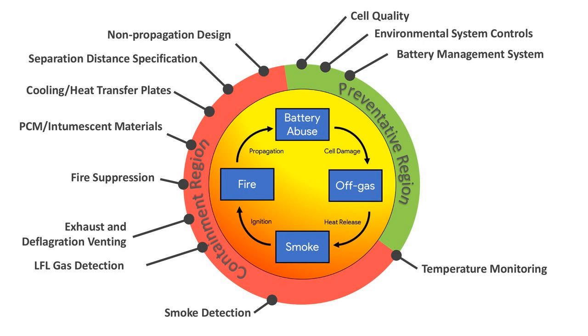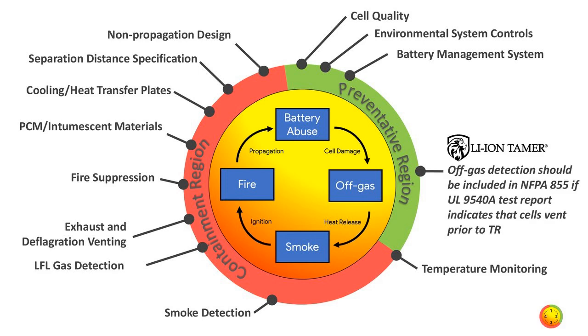But there's a region around off-gas monitoring that's currently really not utilized. This is what we've been looking at within industry to provide additional ways of providing fault detection on these battery systems, where off-gas detection should be included if the UL 9540A test report indicates that a cell vents prior to thermal runaway. If that opportunity is there, then there's a means for detecting that fault.